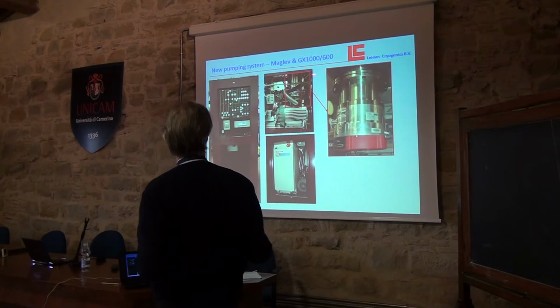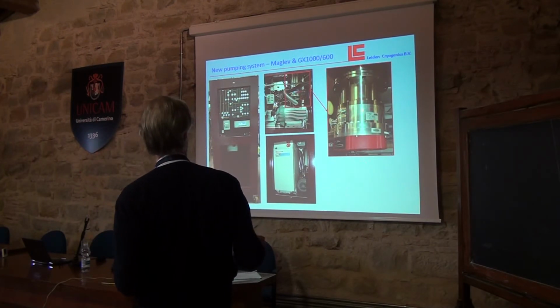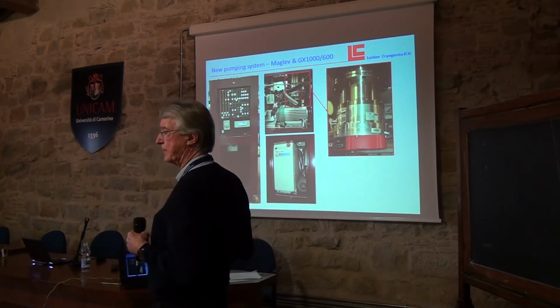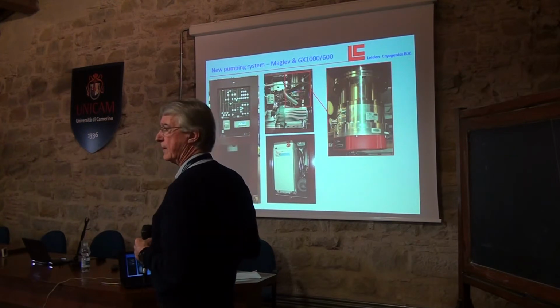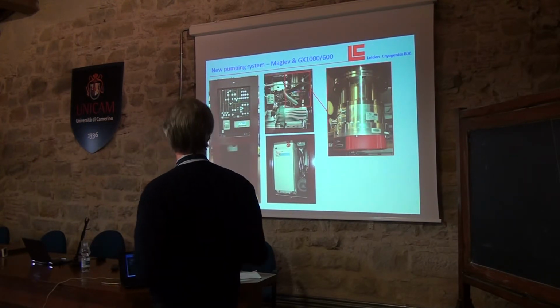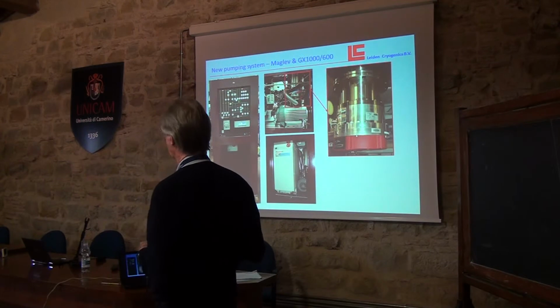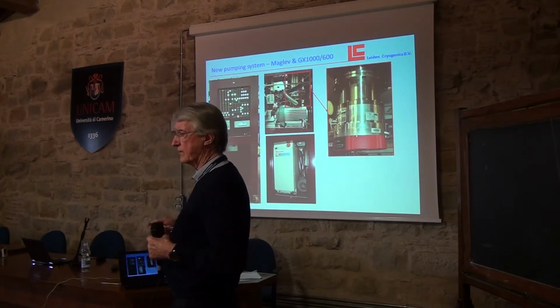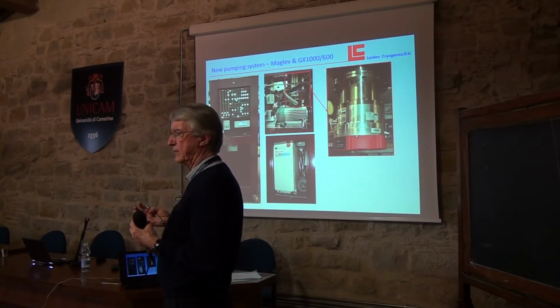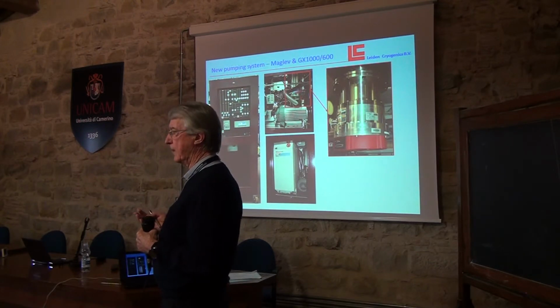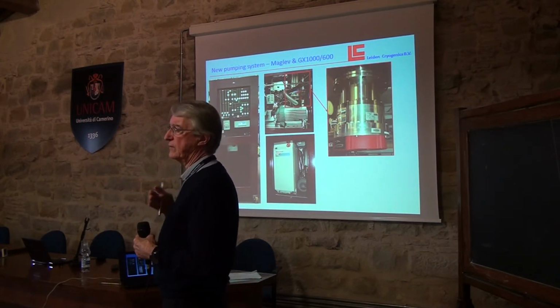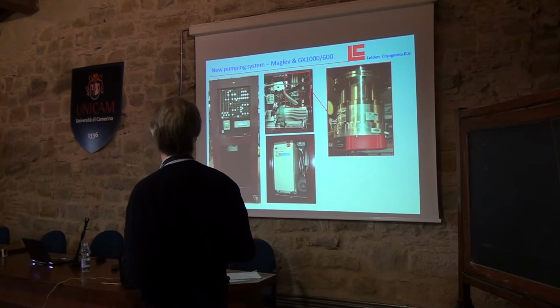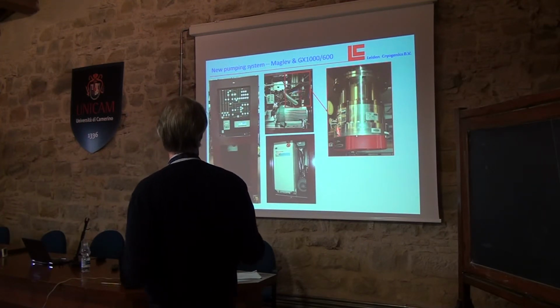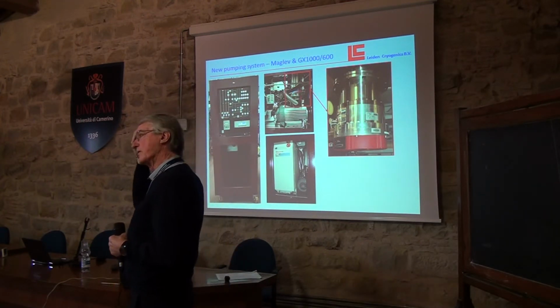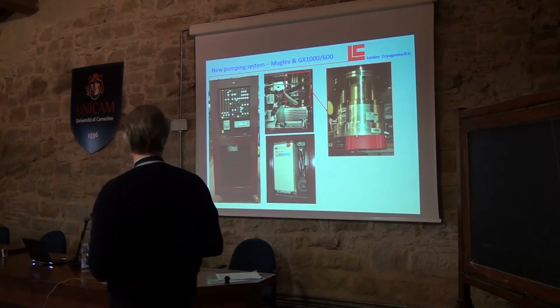The pumping system is also quite new. We now use a magnetically levitated turbo pump that has no vibrations. Most of the concerns of people using these refrigerators is that this vibrates. It vibrates much less than a different machine because it doesn't have a mass going back and forth, just gas. But still, there is some concern, especially for people doing optics and tunneling and so on. So we developed this pumping system.